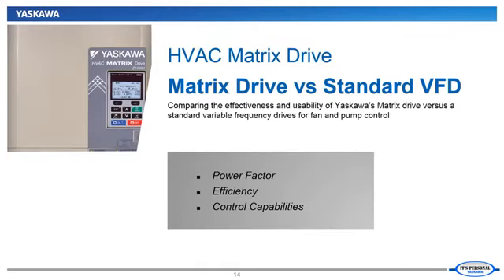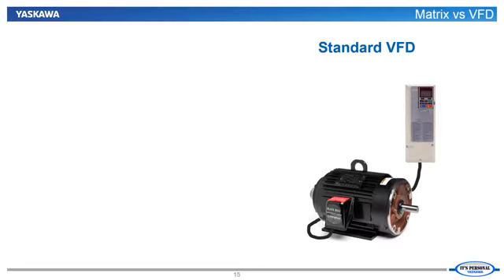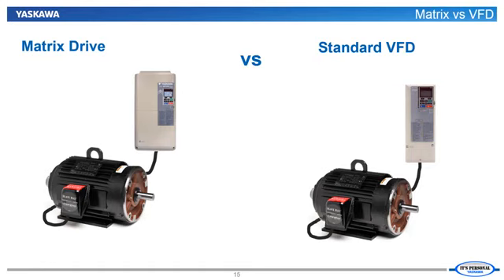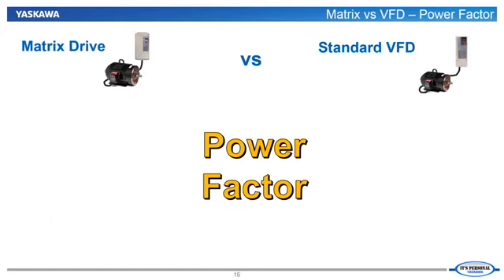The next step in evaluating the matrix drive on fan and pump applications is to compare the unique capabilities of the matrix drive versus a standard 6-pulse VFD. As we have stated, any standard AC VFD has the ability to regulate a fan or pump to only run at the speed that the system demands, thereby eliminating the need for dampers, vanes, or valves to regulate pressure or flow. By automatically regulating speed to maintain demand, the drive automatically optimizes the system's operating efficiency. The matrix can do all that as well, but offers some distinct advantages not possible with a standard VFD solution. Again, let's begin our comparison with a look at the expected power factor performance of each device.